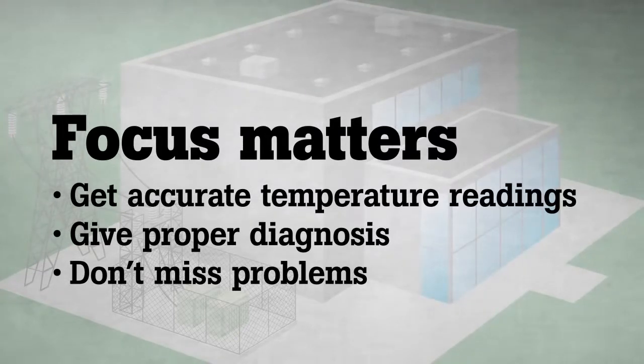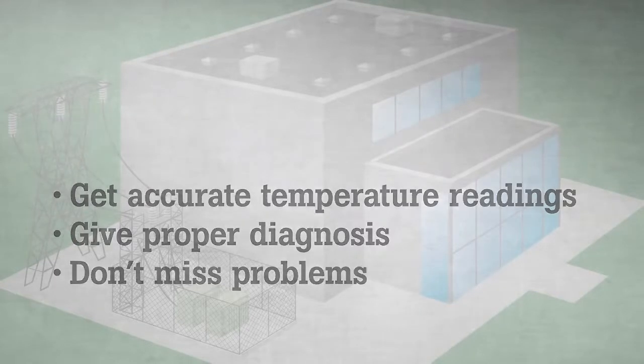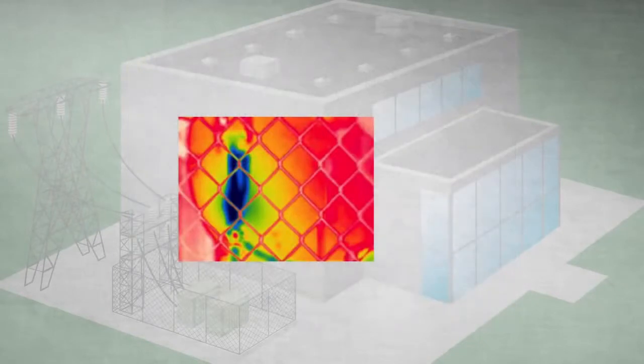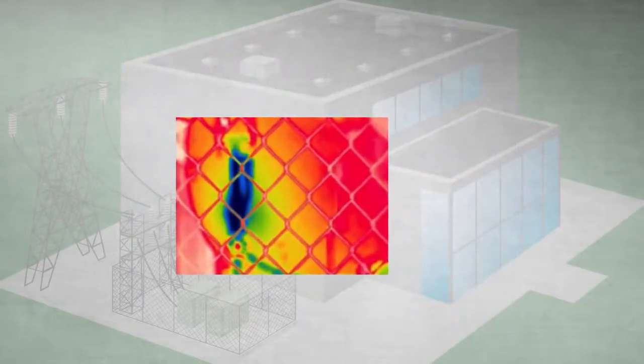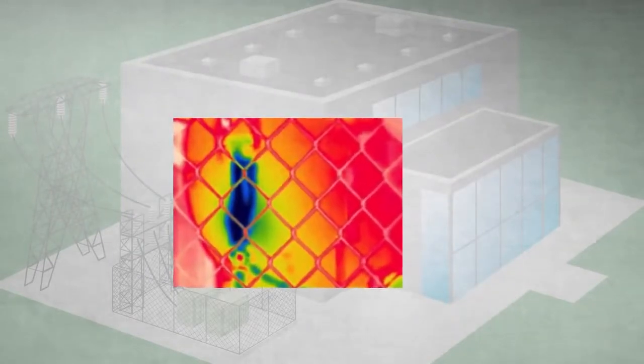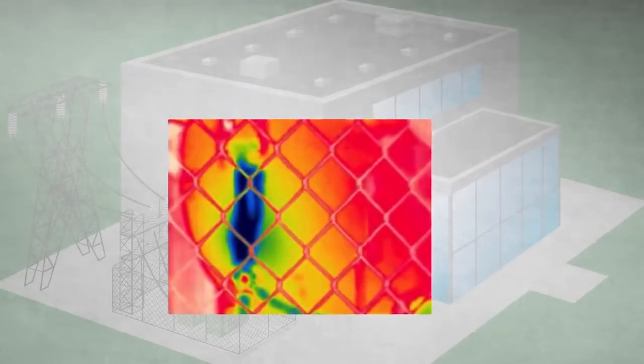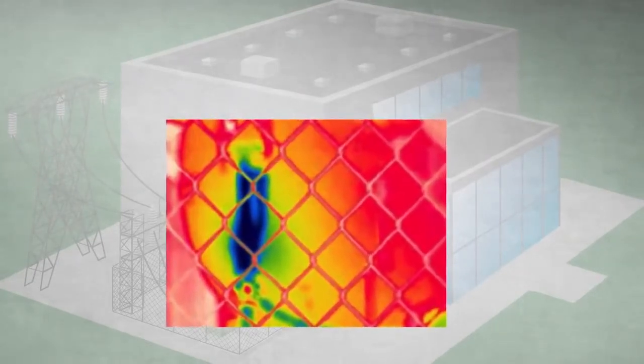Many inspection sites are difficult for passive autofocus systems. In this example, the valve we want to inspect is behind a chain-link fence. With a passive autofocus system, the near-field subject—the chain-link fence—is often what the camera chooses to focus on. Multiple images are often needed in order to get one that will focus on the valve, if it will at all.